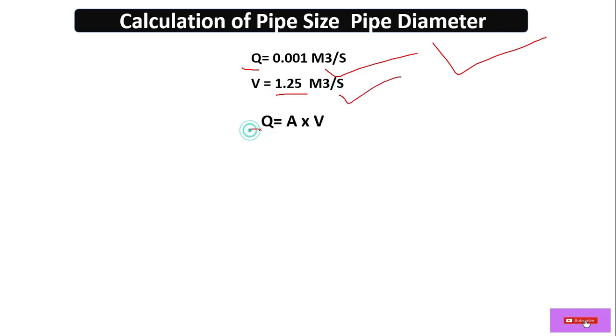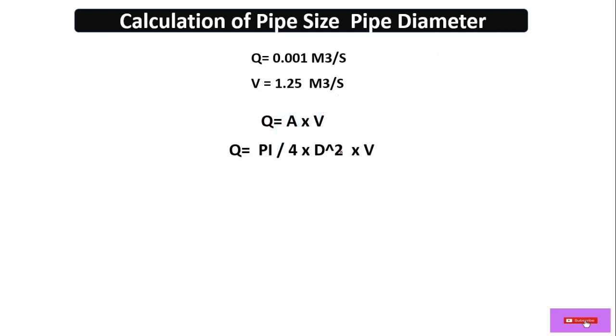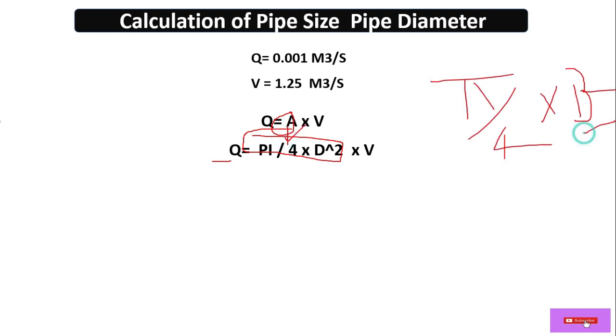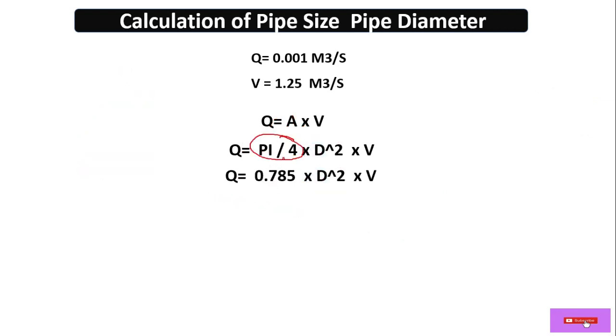Using the formula Q = AV, where Q is discharge, V is velocity, and A is the cross-sectional area of the pipe. The formula for cross-sectional area is (π/4) × D², where D is the diameter. This simplifies to 0.785 × D². Rearranging to solve for D: D² = Q divided by (0.785 × V).